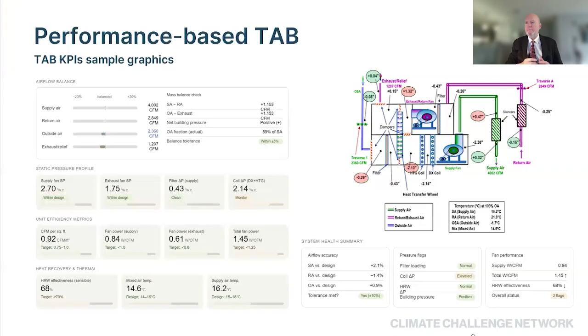And with great respect to everybody, they never are caught, which is why the building often ends up with insufficient airflow or imbalances within the airflow, and undoubtedly excessive fan power. So testing and balancing is a big deal. You need a more rigorous specification, and you need the engineering team to pay very close attention to the results and to fix the things that are not correct. Next slide, please.